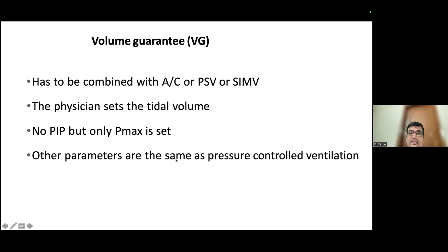So the physician sets the tidal volume as we discussed. The physician does not set the PIP, but only sets the maximum pressure. Okay, and this working pressure actually fluctuates around this maximum pressure, and other parameters like PEEP, rate, TI, depending on the mode of ventilation, FiO2, are set as that of the pressure control ventilation.